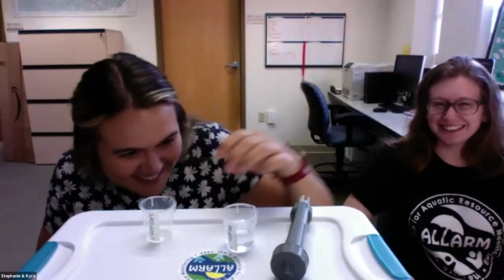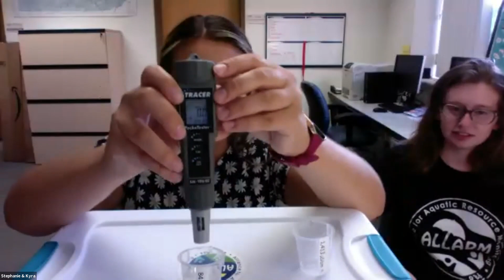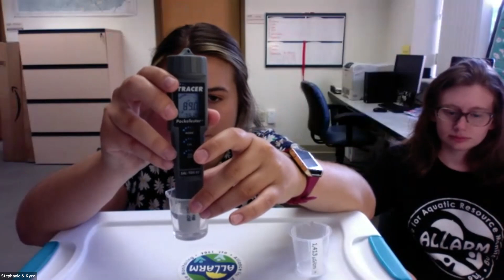Once you've poured out the standard, please place the electrodes into the solution. And as a good practice, we always say keep the meter suspended in the solution versus resting it on the bottom. That's a good practice. If you're out in a stream, you obviously wouldn't want to put your meter, if you had a really shallow stream, into the sediment. And what we're going to do first is allow our meter to stabilize.